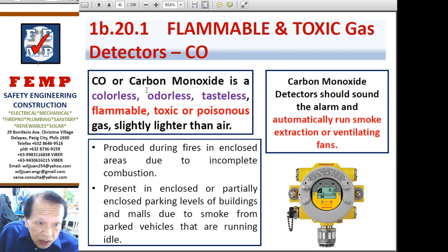So carbon monoxide is a colorless, odorless, tasteless, flammable, toxic or poisonous gas. It is slightly lighter than air, no? It is produced during fires in enclosed areas due to incomplete combustion, and is present in enclosed or partially enclosed parking levels of buildings or malls due to the smoke from parked vehicles that are running. In other words, sometimes in the basement some vehicles are running, and there's a possibility that carbon monoxide is being produced. So the solution there is to install carbon monoxide detectors, which should sound an alarm and automatically run smoke extraction or ventilating fans. So that's the only way, because why?